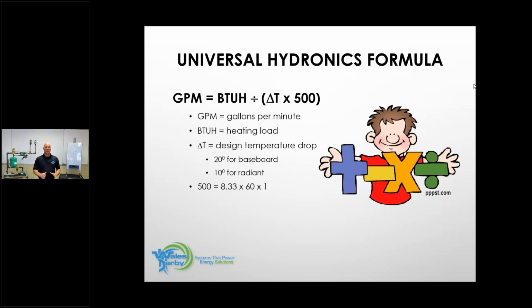So you can utilize that universal hydronic formula two different ways. We can multiply or we can divide. And over the next couple of weeks, you will be using this formula. You will be multiplying. You will be dividing. We will give you a 10-degree delta. We will give you a 20-degree delta. We will give you a 30-degree delta. If it's a 10-degree delta, where the delta T symbol is, you're going to put a 10 there and multiply that by 500. Now every gallon of water has the ability to carry 5,000 BTU. If it's a 30-degree delta T, you're going to put a 30 where that delta T sign is, multiply 30 times 500, and you're going to find that now you can carry 15,000 BTU with that gallon of water. But the majority of the time, when you're using this formula, you're going to put a 20 where the delta T is, multiply that by 500, and that gallon of water has the ability to carry 10,000 BTU.